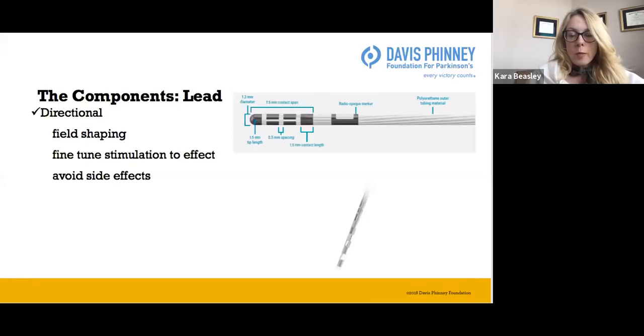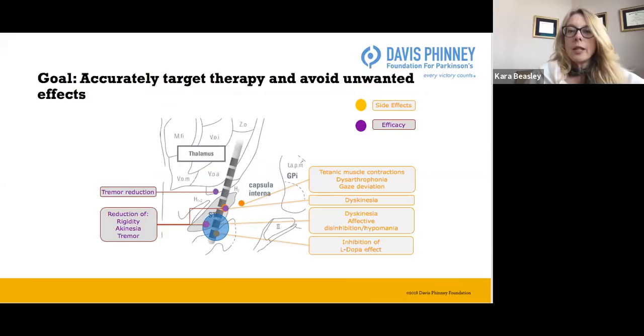If you advance to slide number 6, I can show you what I'm talking about. Our goal is to accurately target therapy and avoid the unwanted side effects. As you can see, the blue circle represents where the electricity would be placed, and that's with a traditional ring. You just get a circle, and the purple is where we would like the stimulation to be. However, the blue circle covers some areas that would cause some side effects. If you advance to the next slide, it shows a directional lead placed in the STN nucleus with only 2 of the contacts presenting electricity. So now, instead of having a circle, we're able to shape that field and drive stimulation away from side effect areas while capturing stimulation in the structure of the brain that will actually affect Parkinson's. So it gives an overall better efficacy.